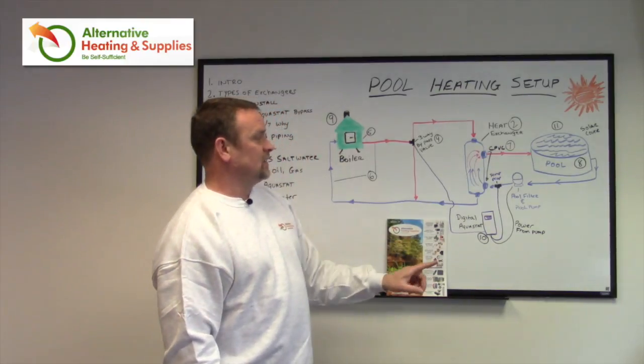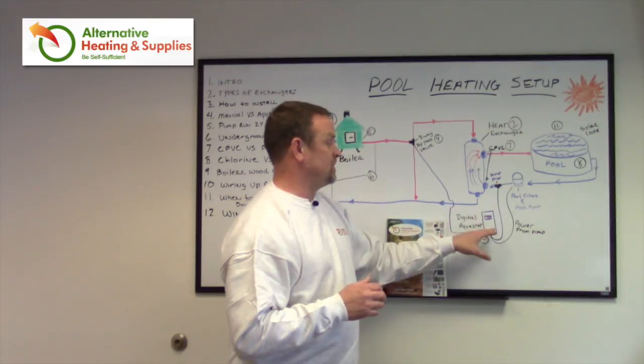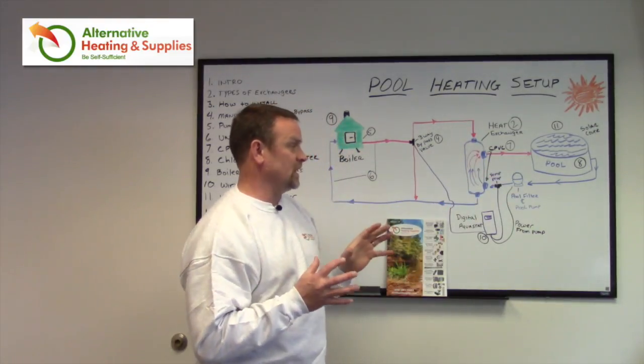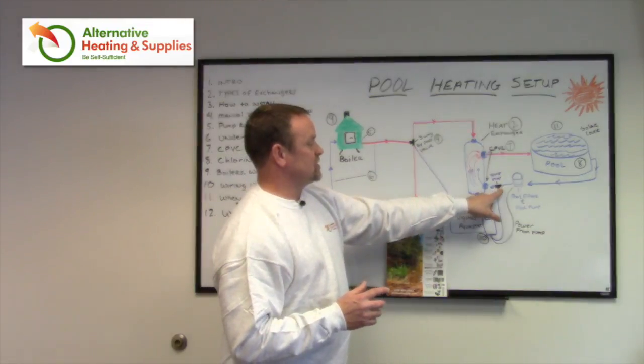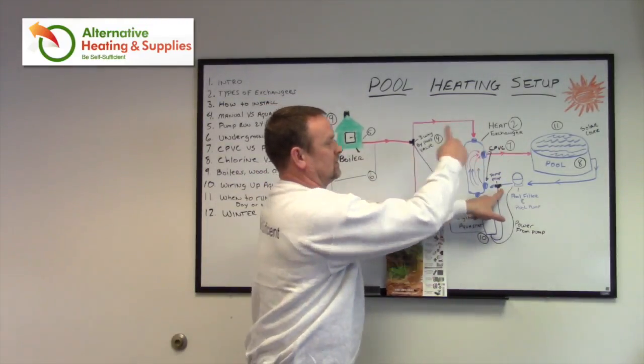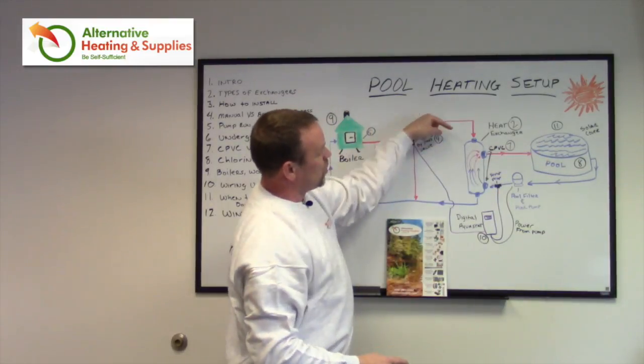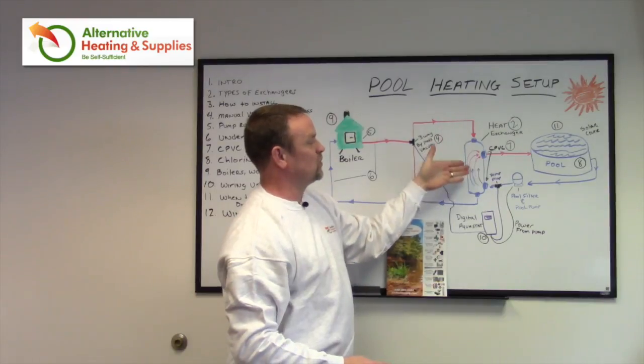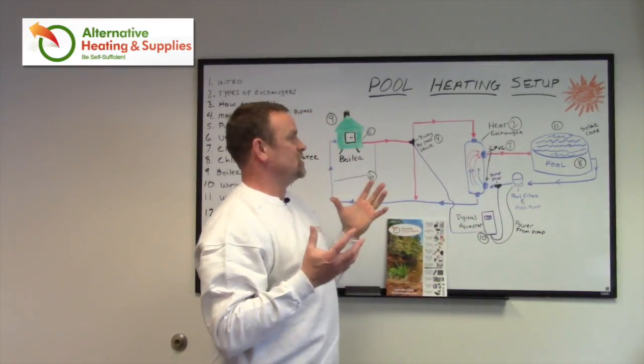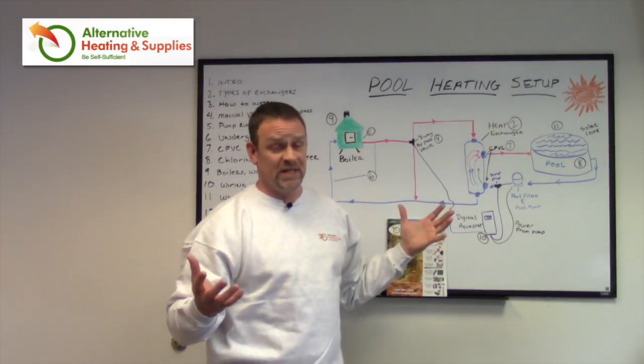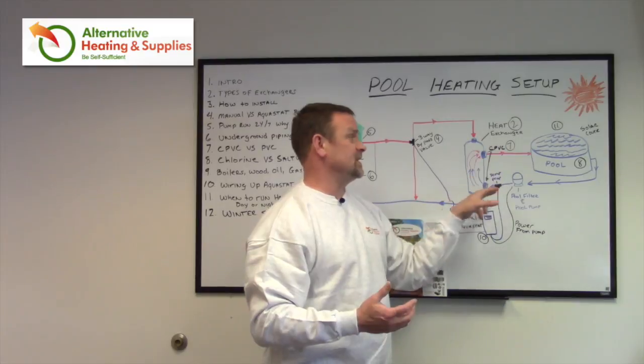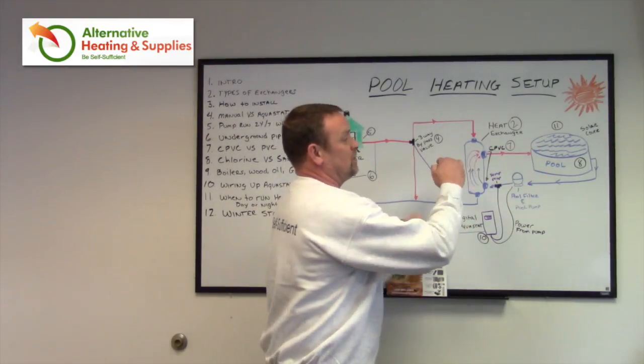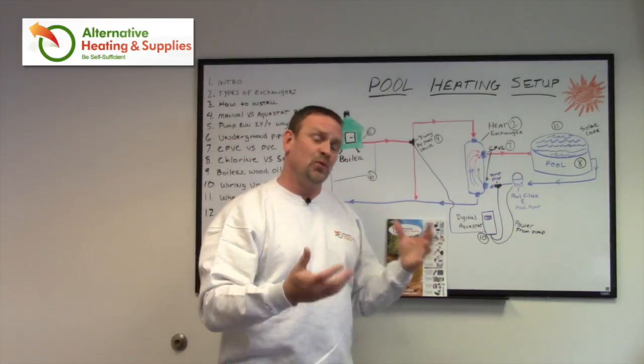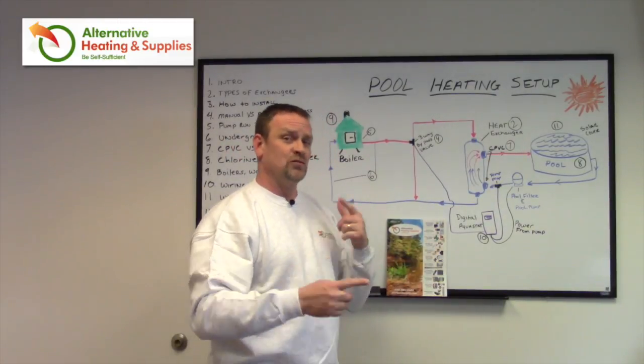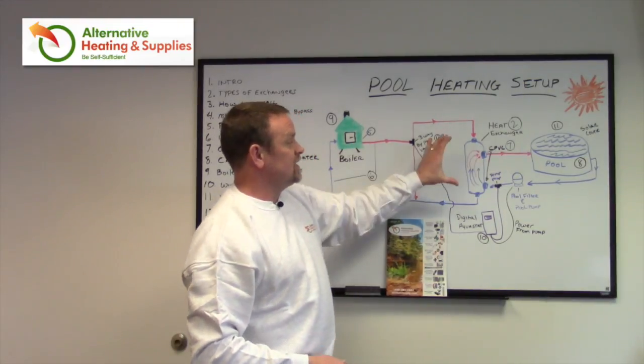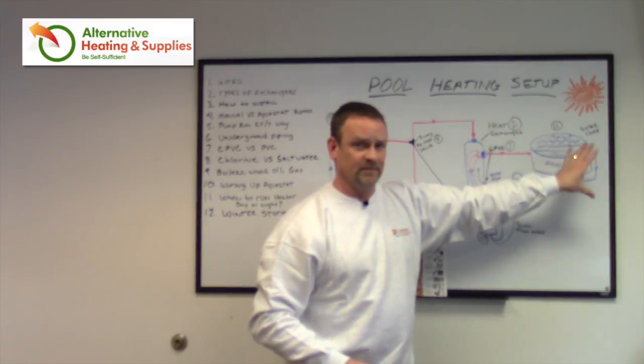The reason you want it powered while the pool filter is running is that if the aquastat senses the water is cold and the pool filter isn't running through this loop, the water going through the heat exchanger would heat up the water on the pool side to 180 degrees, doing nothing useful. Depending on the PVC piping you have, that hot water will slowly get pushed toward the pool, and pool liners and fittings don't handle those temperatures well. That's why we only want water circulating in the tube and shell heat exchanger while the pool filter is running. I hope that makes sense. If not, just give us a call and we'll explain it in more depth.